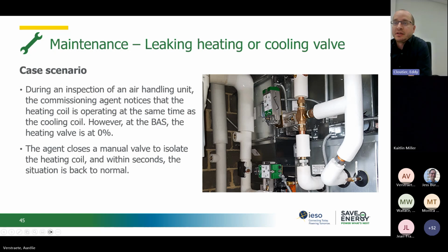So, first case scenario: during an inspection of an air handling unit, the commissioning agent notices that the heating coil is operating at the same time as the cooling coil. It could be detected by using an infrared thermometer. However, at the BAS, the heating valve is completely closed. The agent can close a manual or isolation valve to isolate the heating coil, and within seconds, the situation is back to normal. This shows that we probably have a leak at the heating valve.